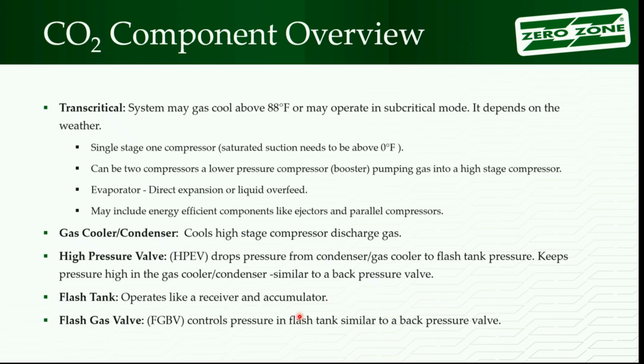Comes out of the gas cooler and we drop that pressure. So we go in, we've got a plasma. It's not liquid, it's not vapor necessarily. We drop the pressure on it. Poof, instantly we get a liquid and a vapor out of it. So that's what that valve is doing. It's there to keep the pressure up high enough, and then when I drop the pressure down, I get a liquid and a vapor.